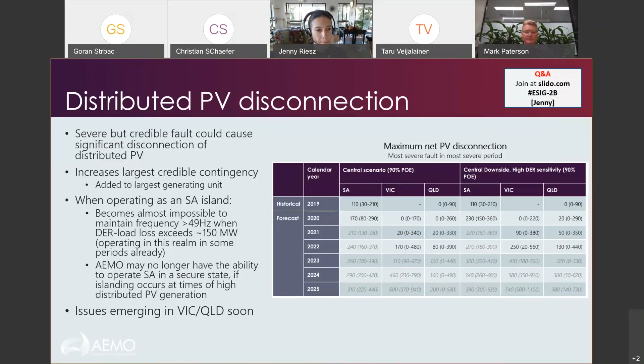So what do we need to do to manage this? There's a whole suite of things underway. The first thing is to improve the performance of the distributed resources themselves so that they don't disconnect in these sorts of disturbances. So the main mechanism here is Australian Standard 4777, AS 4777. There's a review process underway, which Taru is actually leading, working to improve those standards and make sure that inverters ride through in these kinds of events.